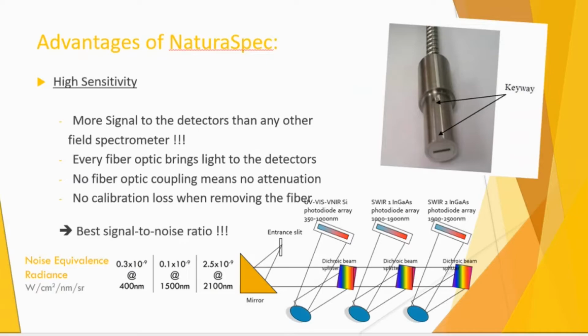Because this fiber is precisely machined and aligned with the entrance slit to the spectrometer, we don't have any loss of calibration if we remove that fiber from the instrument. That's one of the big advantages of a Spectral Evolution instrument that we'll see a little bit further down: if your fiber were to break, you can remove it easily, replace it with a new fiber, and not lose any calibration. So by paying attention to the fiber and to how the signal enters the instrument and goes through each detector, we are able to achieve a very good signal-to-noise ratio. For people who want to check the specification, we express the signal-to-noise in noise equivalent radiance, and those numbers, as you can see, are very small, in the 10 to the -9 range.